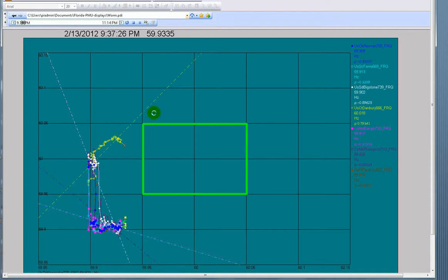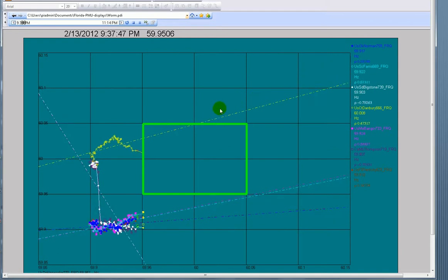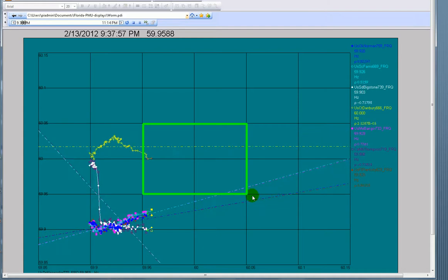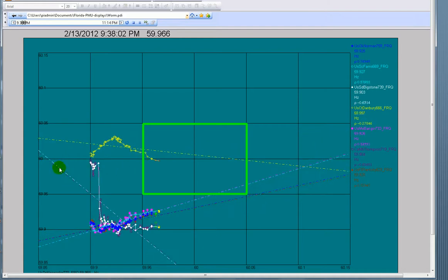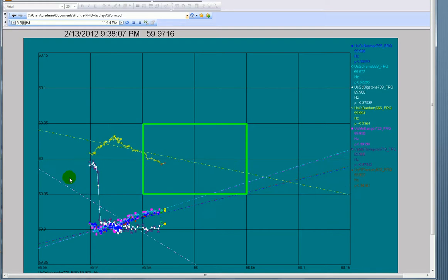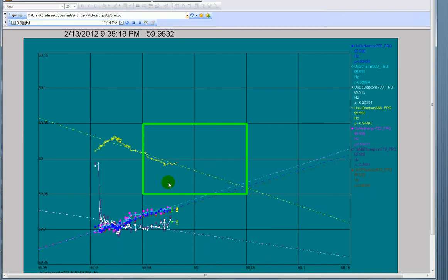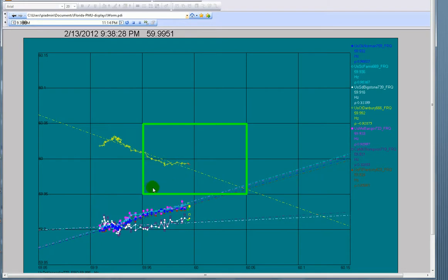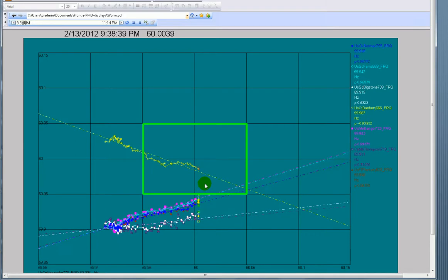And we can clearly see now that Danbury is starting to operate synchronously with Knoxville. It's because the slope of this line is now positive. So we have Danbury and these stations here all operating positively, but we still have negative correlation on these two stations. So you can see the system is now trying to recover to get back into what we call a safe region of state space. This is the plus or minus 0.05 standard from NERC.